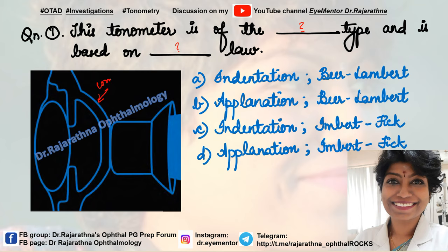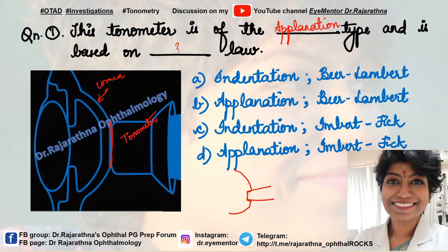You can see the cornea here and the tip of the tonometer touching the cornea, and what it is doing on the cornea is just flattening the corneal surface. So it is definitely applanation type, because we have two types: applanation and indentation. If it were indentation, it would have indented the corneal surface.